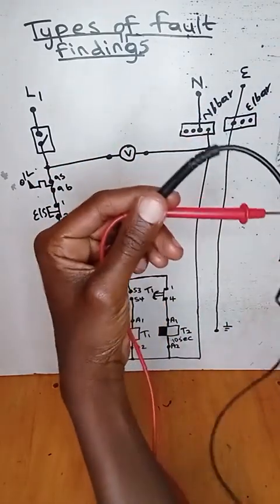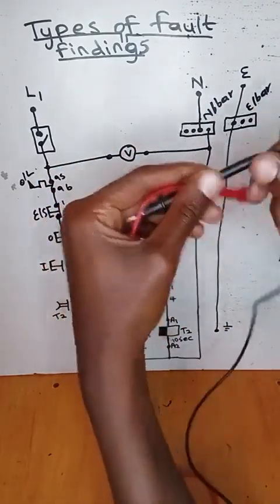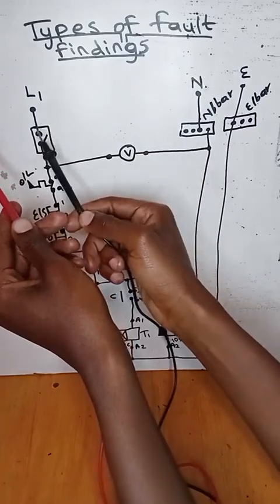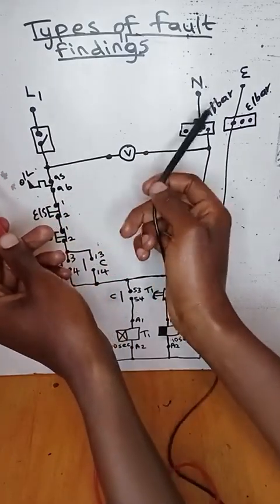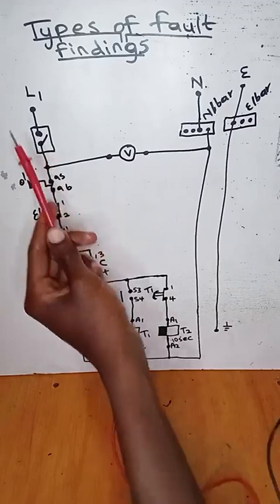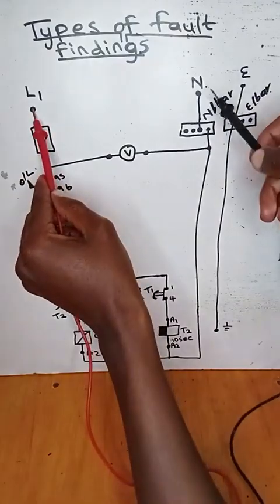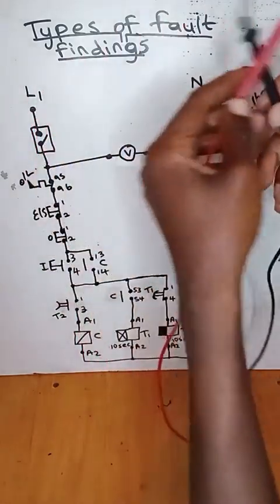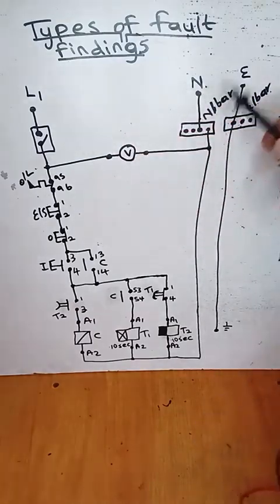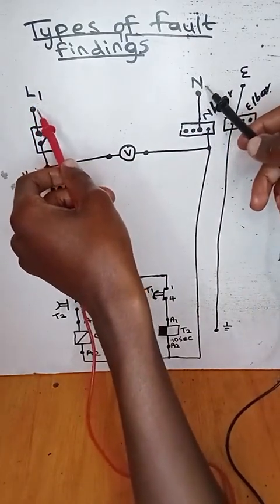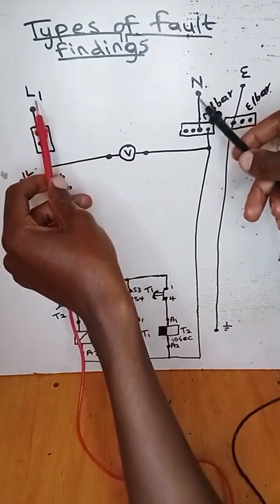from the DB box, right? It's off, so there's no power in these three wires of single phase, right? So we'll test live 1 and neutral to check if live and neutral are connected or not connected. If they are not connected, then we are good.